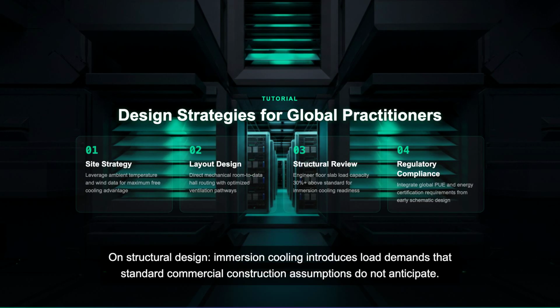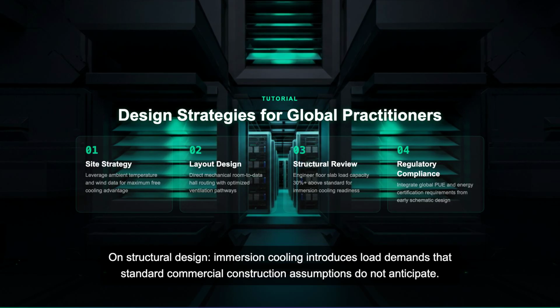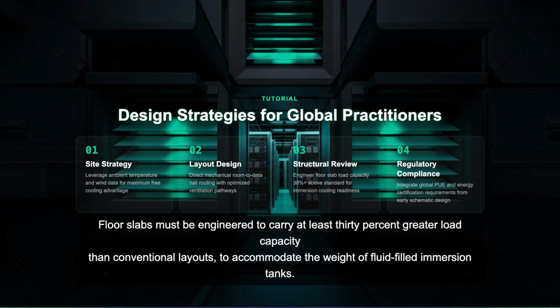On structural design, immersion cooling introduces load demands that standard commercial construction assumptions do not anticipate. Floor slabs must be engineered to carry at least 30% greater load capacity than conventional layouts to accommodate the weight of fluid-filled immersion tanks.